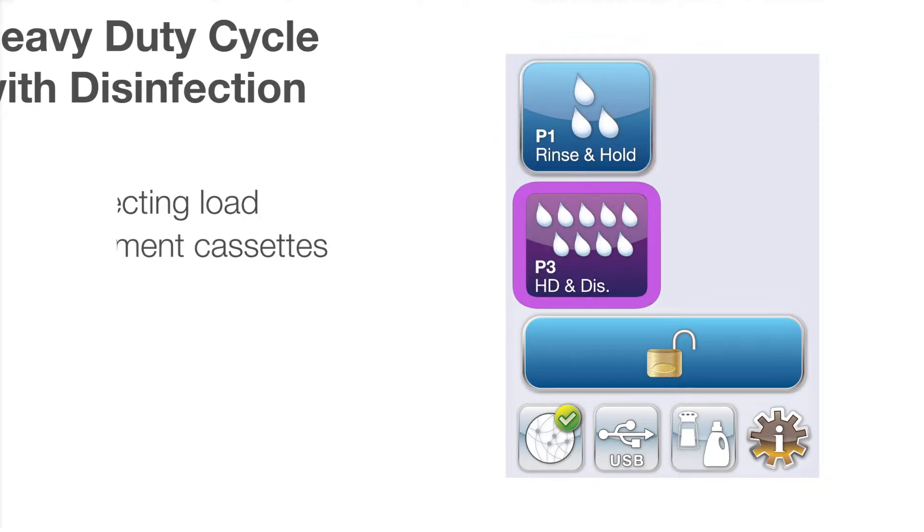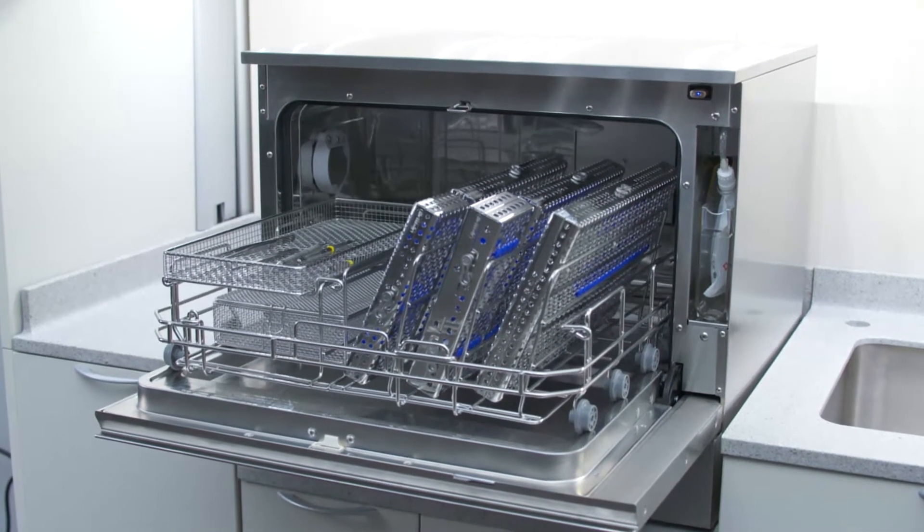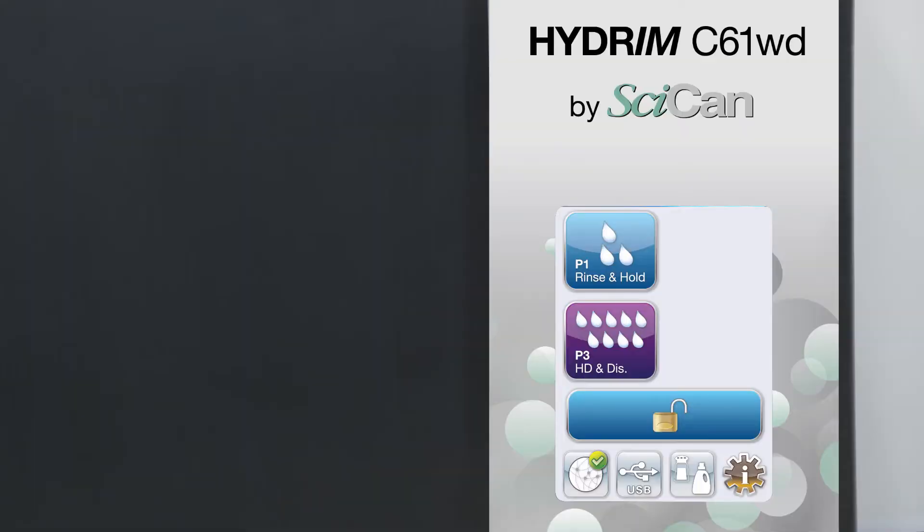P3 heavy duty cycle with disinfection: use for heavily soiled instruments and cassettes. For this type of full load, we will select P3 heavy duty wash cycle with disinfection program.